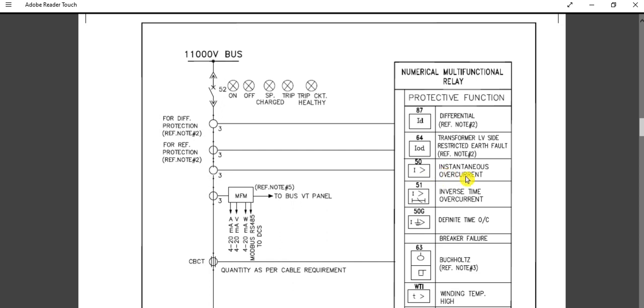The functions fed by this CT are: 50 — instantaneous overcurrent without any time delay; 51 — inverse time overcurrent; 50G — earth fault overcurrent; and breaker failure function. These are the protective functions required for this feeder. This current transformer is connected accordingly to support these functions.